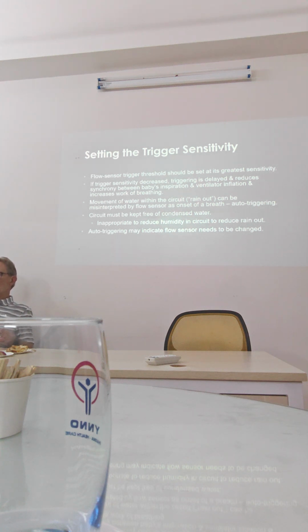stimulus to trigger inspiration. Because if you have the trigger sensitivity set wrong, the baby actually has to take a significant breath before the ventilator triggers. So your synchronicity between the baby taking a breath and then the ventilator firing is delayed, and that actually increases the work of breathing. The problem with trigger sensitivity is you can get what we call auto-triggering. So auto-triggering is when the ventilator thinks the baby's taking a breath, but it's really not. And one of the more common reasons for that is you get water build up in the circuit, and you'll see the water sort of bubbling in the circuit, and that can be enough to trigger the ventilator, and auto-triggering occurs.